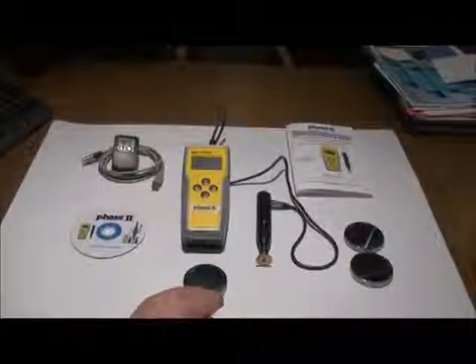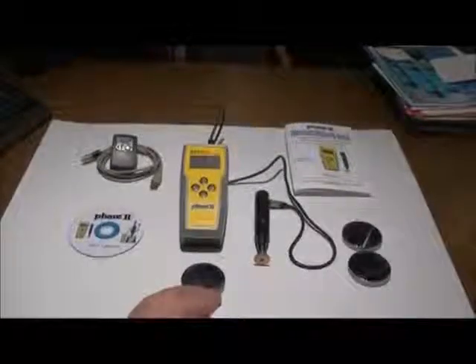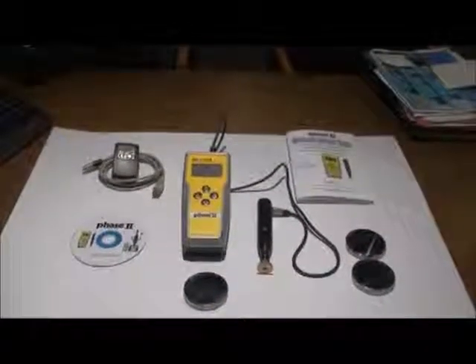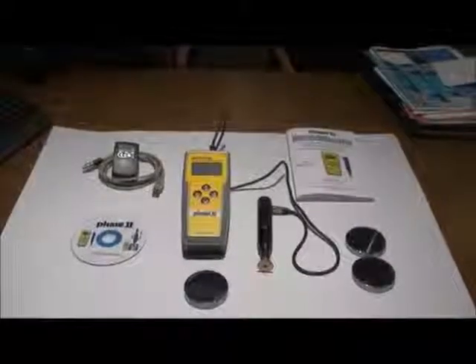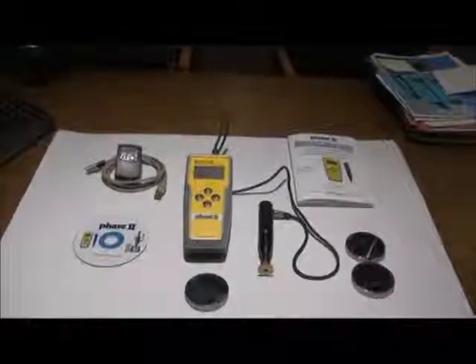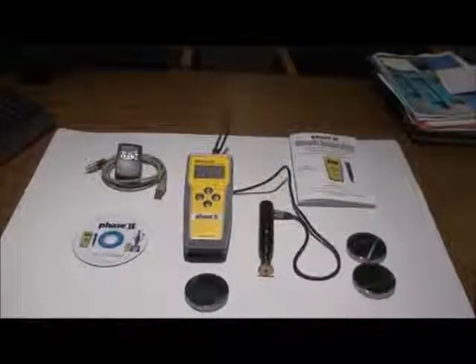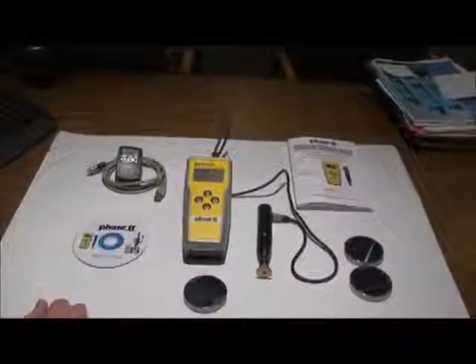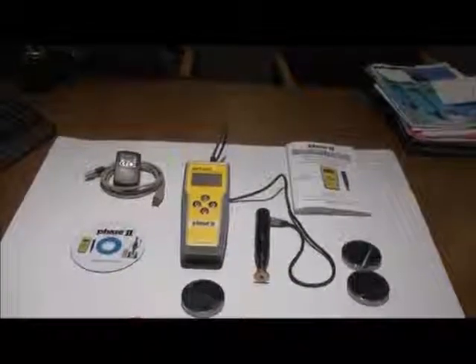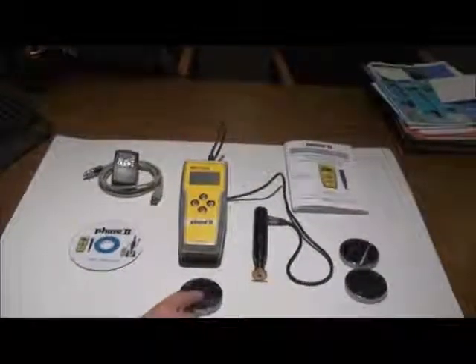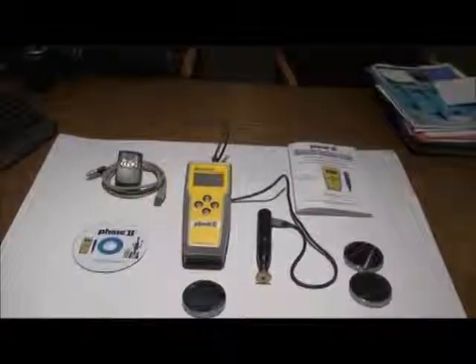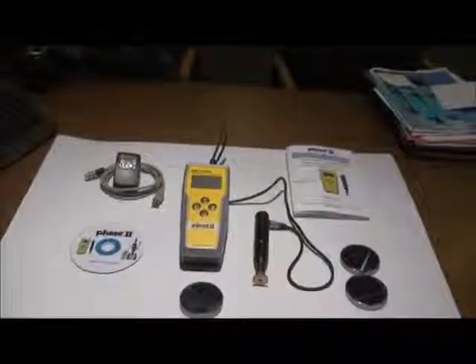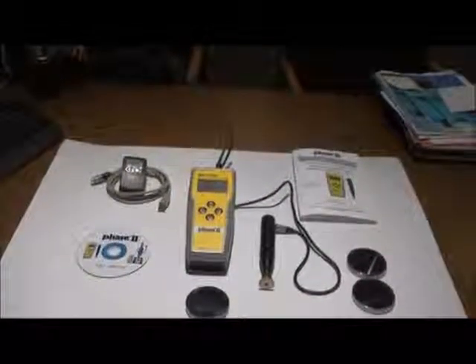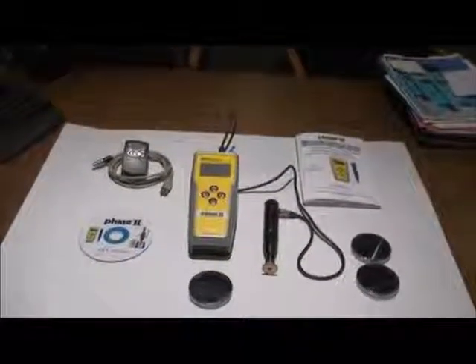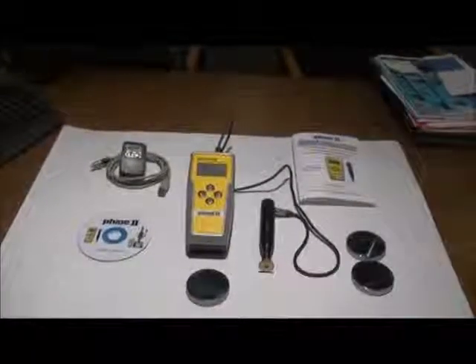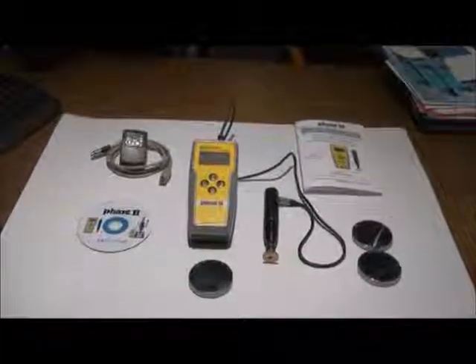Coatings or layers need to be 10 times the indentation depth of test, which will vary depending on the load force used and approximate hardness of material. Should you have questions on this parameter, please contact Phase 2 directly. The next parameter is surface roughness. If you are testing precision machine parts with a surface finish of better than 100 microinches or 2.5 microns, then you can use the 1.5 kilogram load probe for most of your applications. For those surfaces which are rougher, the 5 kilogram load has an approximate maximum of 4 microns or 160 microinches.